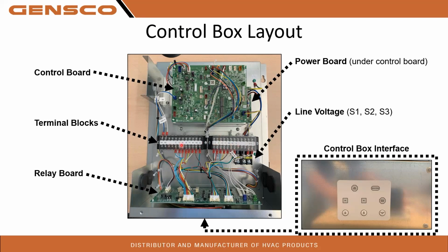You have two separate terminal blocks in here for low voltage wiring. Terminal block A, TBA, is for your furnace wiring. TBB is for your 24-volt thermostat controls. For those of you that have used the 24-volt interfaces previously and other equipment, this is a little different. Your thermostat will not wire into that 24-volt interface. It is going to wire onto this TBB terminal block. That wire will come on down to this relay board down here and will communicate with the system. Or if you have that 24-volt interface, it's going to come back up. We'll get into that. We have a slide of that connecting to a PAC 445 interface and show you how to work all that.